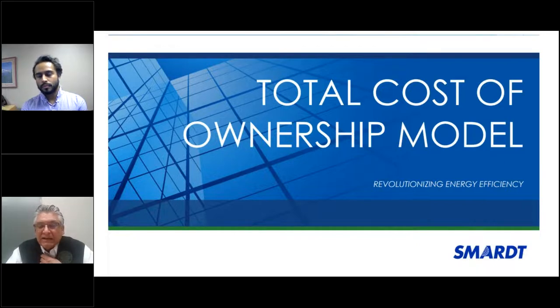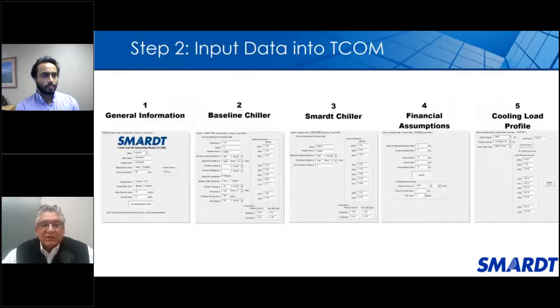And so we've actually come up with a way to look at the total cost of ownership by looking at the general information for the selection of the chiller. Let's take a baseline chiller. Let's say we're looking at a design for a Smardt oil-free machine versus a more traditional centrifugal that uses oil for its compression, and look at the efficiencies and the pressure drops, all things that relate to the machine's performance, right? Kilowatts per ton, full load capabilities, part load capabilities, turn down, and then also the water pressure drop through the barrels. Maintenance obviously is another thing to consider, and to make sure that you're looking at all those things combined.